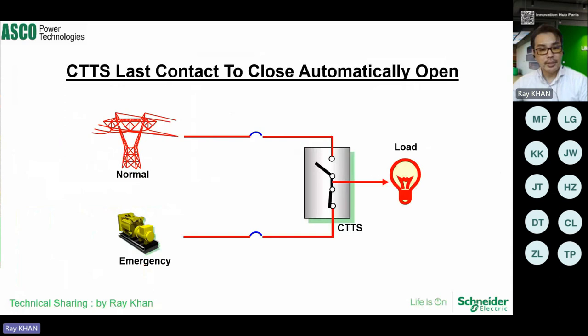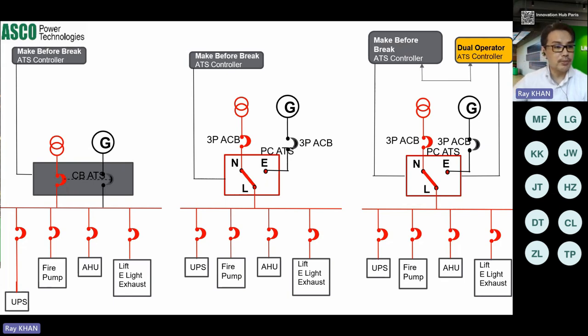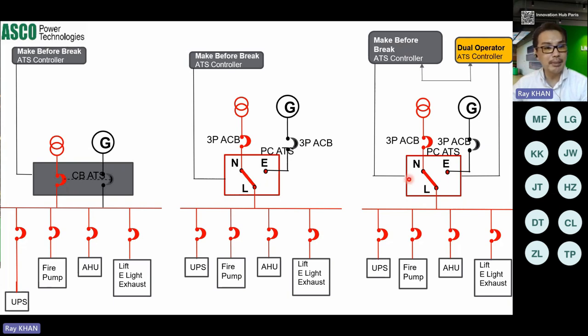Comparing make-before-break using circuit breakers versus ATS: on the left, ATS made from circuit breakers — if the controller fails, the circuit breaker can no longer function. In the center, an ATS with only one controller — if the controller fails, the ATS cannot function. On the right, an ATS with dual controllers: the first controlled by the normal supply position, and the second controlled by the emergency supply position, providing redundancy.